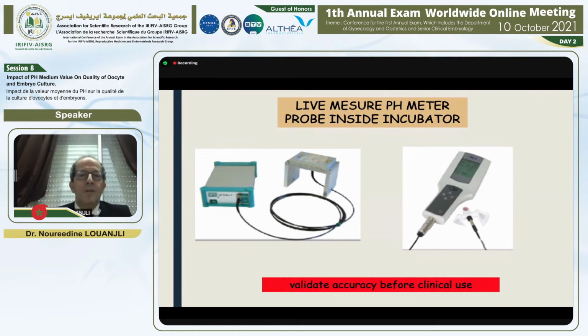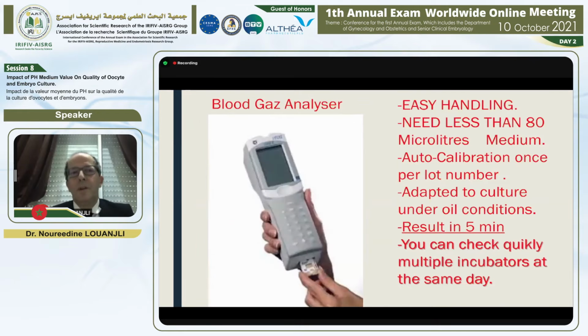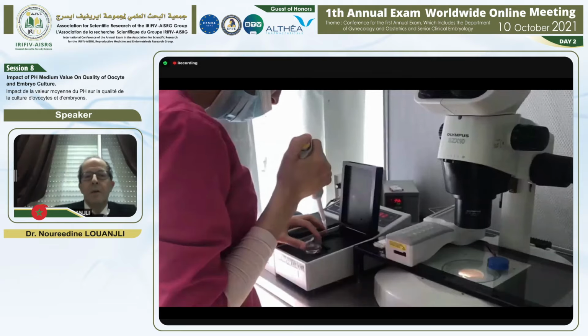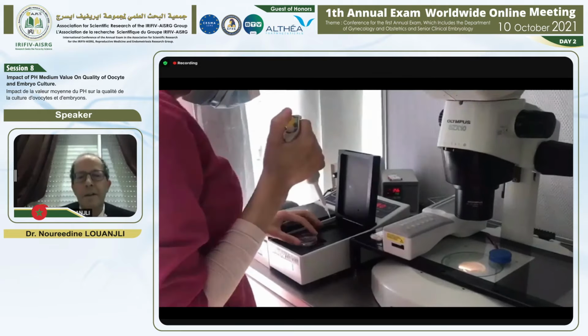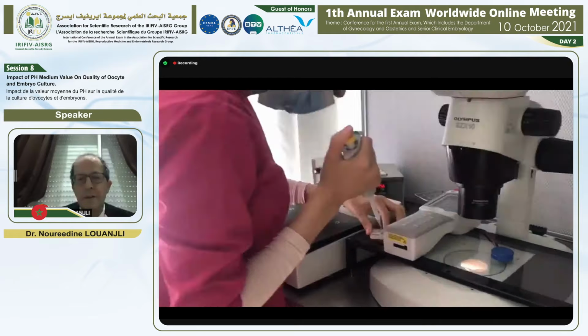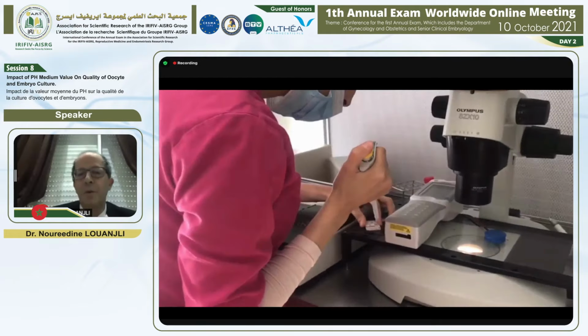Our choice is a blood gas analyzer. It needs less than 80 microliters, has auto calibration once per lot, and is adapted to culture under oil. The result comes in 5 minutes, and you can quickly check multiple incubators on the same day. We use it in our lab. It takes less than 30 seconds to get the pH of your working medium.